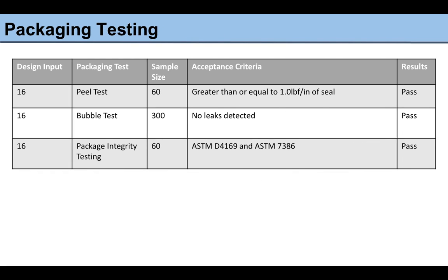We also conducted packaging testing to make sure that our packaging remained intact and kept the device safe. For our packaging testing, we performed a peel test with a sample size of 60 because it is a variable test and also based on the risk levels associated with the design input. The acceptance criteria for this test was a force greater than or equal to 1 pound force per inch of seal when packaging was peeled apart on an Instron. This test passed.